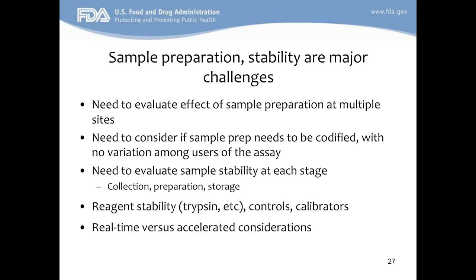Additionally, because these workflows are so complex, instead of taking 20 minutes to an hour to get to the result of the test, as is the case with many automated immunoassays, the process could take many hours or perhaps even several days to go from collection to sample preparation. There may be stopping points along the way where samples need to be stored, and the sample stability would need to be evaluated at each of those stages to understand how storage and preparation over time is affecting the stability of the analyte and the result of the test.